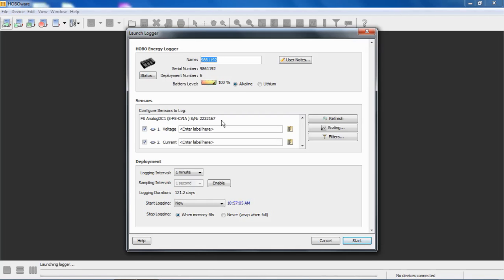These modules are aligned in HoboWare in hierarchical serial number order. So if I had three modules in here, they would be aligned here in the sensors block of HoboWare in order of serial number, not by how they are plugged into the module, the physical module ports. This is a bus, it's a common bus, so HoboWare always aligns these in serial number order, lowest to highest, no matter where they're plugged in.